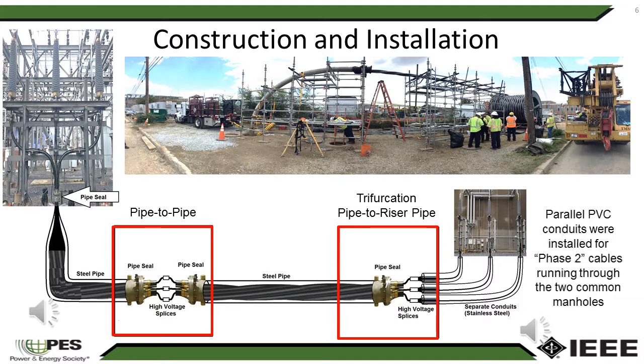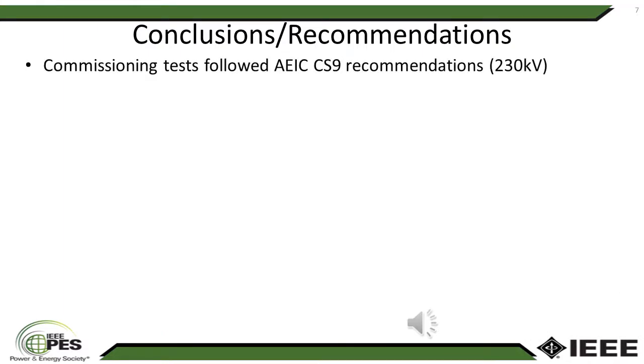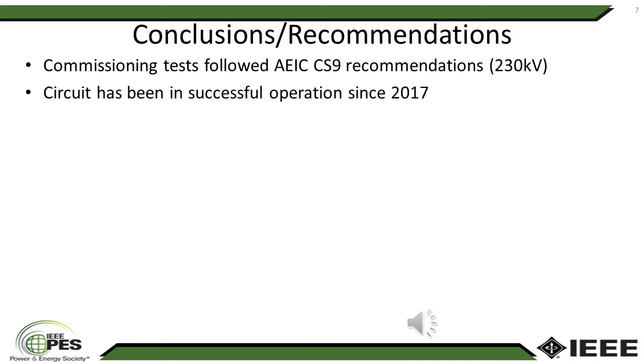Parallel PVC conduits were installed through the same manholes for the second phase of the project, when the circuit would be converted to 230 kV operation. Commissioning tests followed AEIC CS9 recommendations for a 230 kV system, including an AC high pot and partial discharge monitoring. The circuit has been in successful operation since 2017.